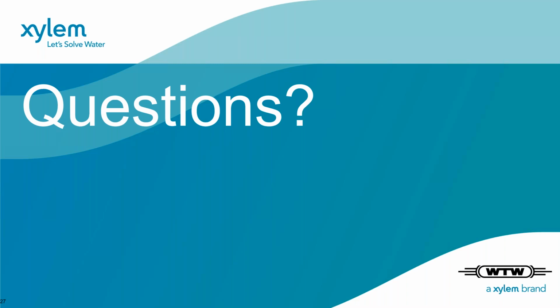Thanks, Natalie. The next question is concerning the blue method and the yellow method. One of our audience understood that the yellow method is quite good at low ranges. So why is the Alyza using the blue method? So the yellow method, the known molybdenum-vanadate method, is normally for orthophosphate measurement, and there is also a blue method for orthophosphate measurement. For ammonium, you have different standard methods, or you can use an ISE for measuring ammonia or ammonium, and the indophenol blue method as a standard method. And this is really also in the lab a standard method for measuring low concentrations of ammonium.